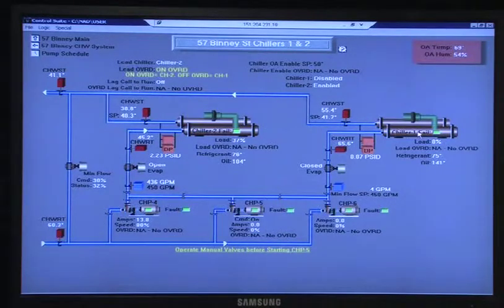The only reason I say that is because they're two 500-ton chillers, and in the worst-case scenario we had out there, we were only at about 75% of capacity of even one chiller. It never turned another one on. It was coasting when we had 97 degrees out. If you look underneath the chiller that's running, see that load? It's 37%. When you see it stuck over 95% for a period of time, you're close to starting another chiller.